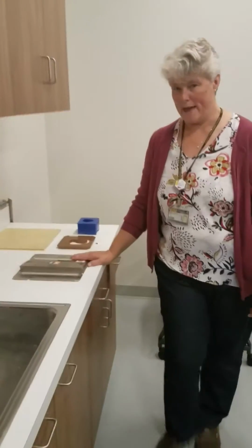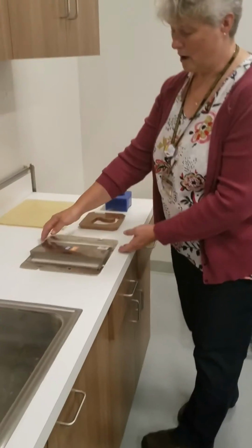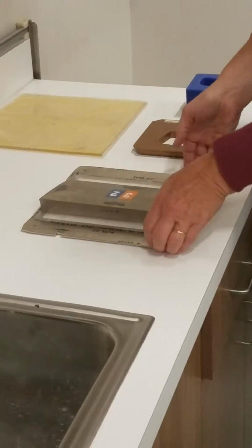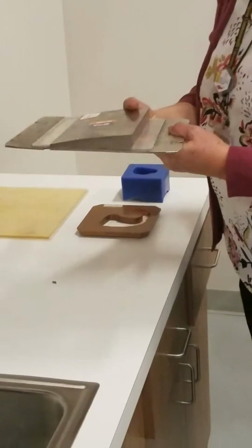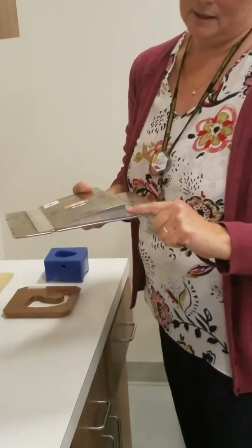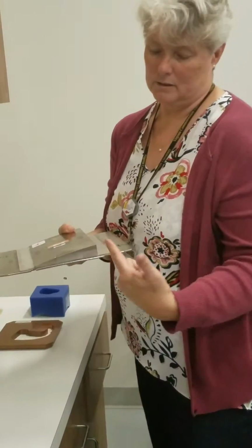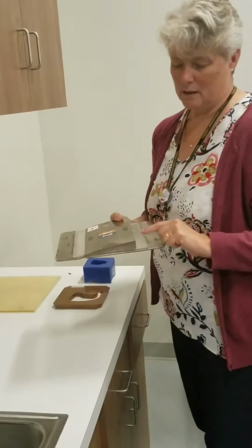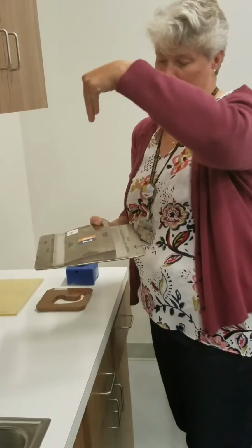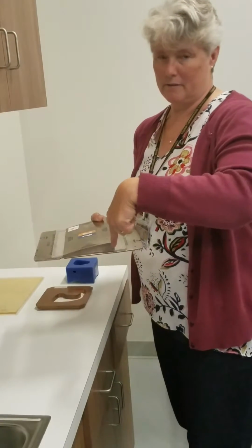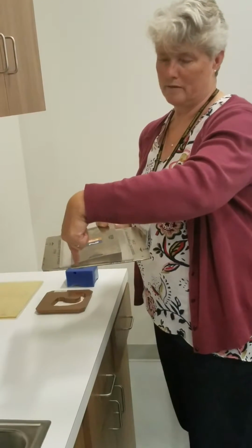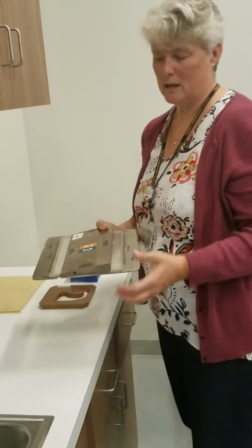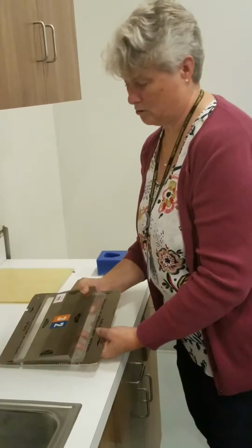This is a wedge. This is used to modify the beam. So you can see this is actually very heavy, and it's thicker on one end than the other. So this is the heel, and this is the toe of the wedge. And you can appreciate that if I had a radiation beam entering here, less of it would get through here, and more of it would get through here. So it changes the shape of the radiation dosimetry.